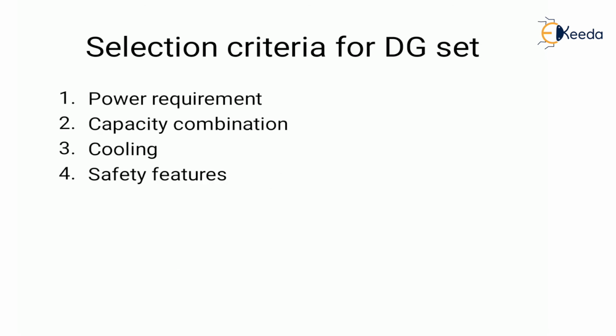So now let us see what are the selection criteria for a DG set. So first, the most important factors are the power and speed of the engine. So first point is power and speed requirement. The power requirement is determined by the maximum load. The engine power rating should be 10 to 20% more than the power demand by the end use. This is because this prevents overload on the machine by absorbing the extra load during the starting of the motors or switching of some types of lighting system, or when the wear and tear on the equipment pushes up its power consumption.